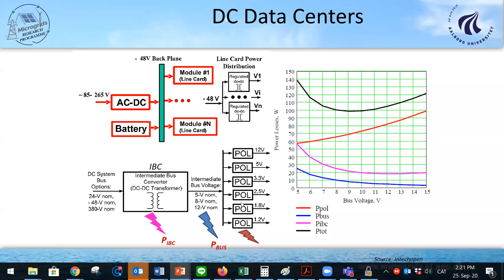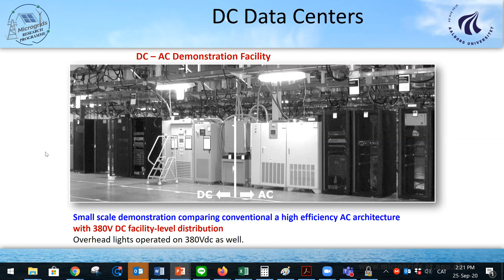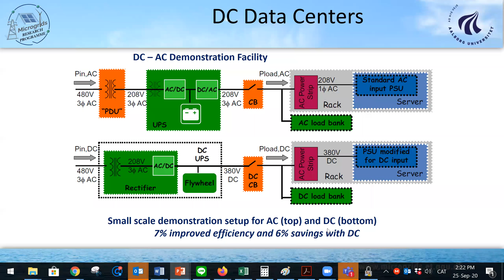This is just one example from Intel. They built the same infrastructure for AC and for DC to support a data center, building essentially the same equipment but adapted for both possibilities. They found 7% improved efficiency for that case, and 6% savings if you move to DC. So the conclusion is: if you're building new, it's good to have a DC data center. If you have to retrofit, it's really difficult to justify economically.